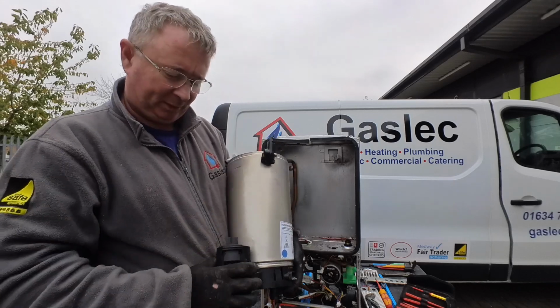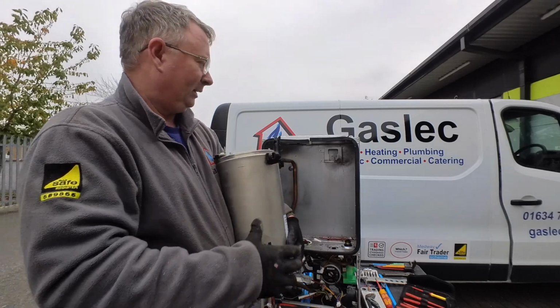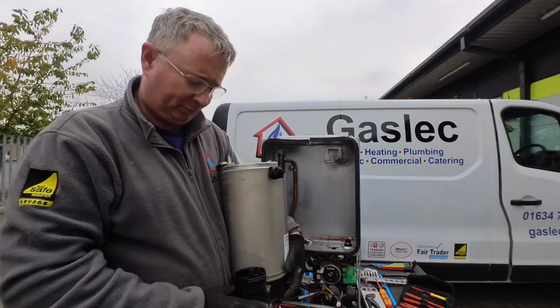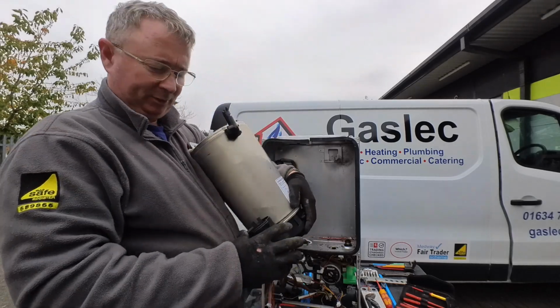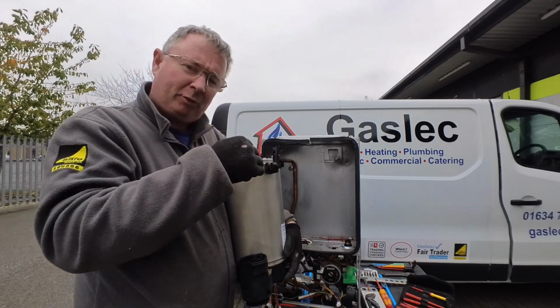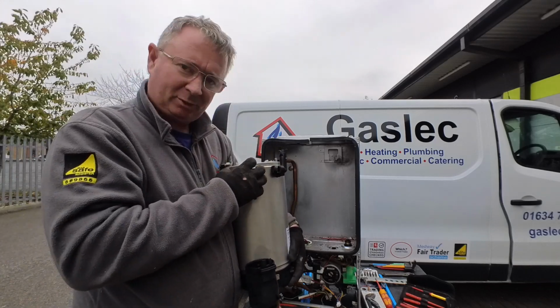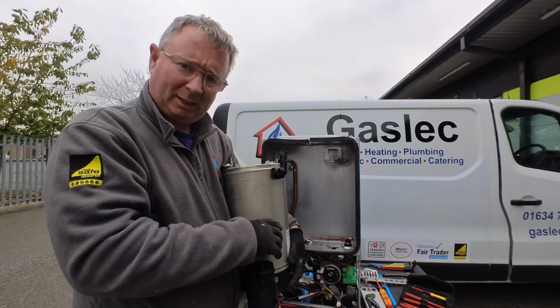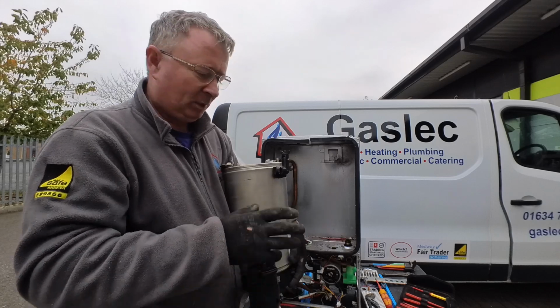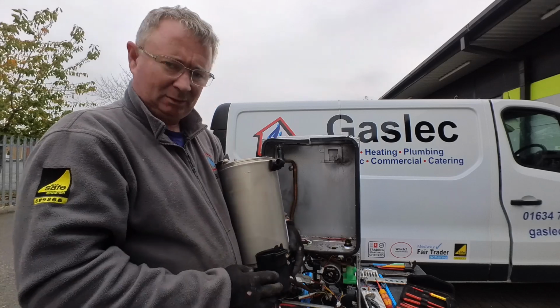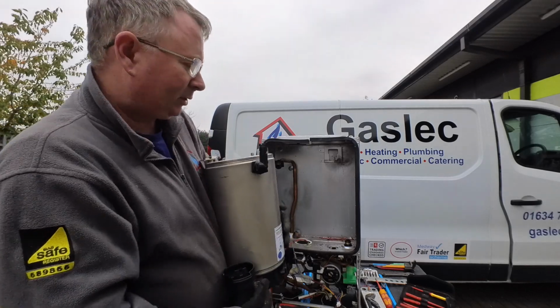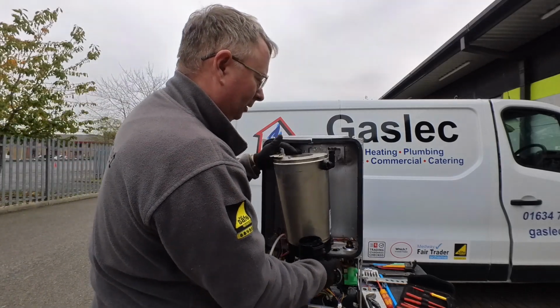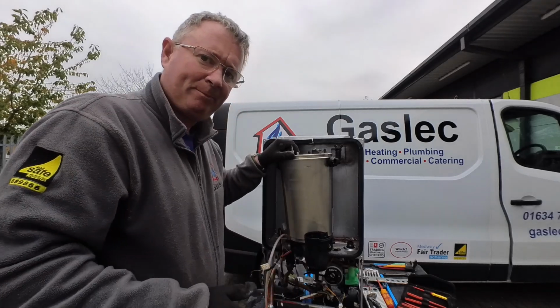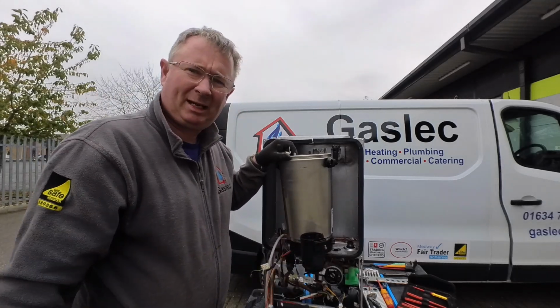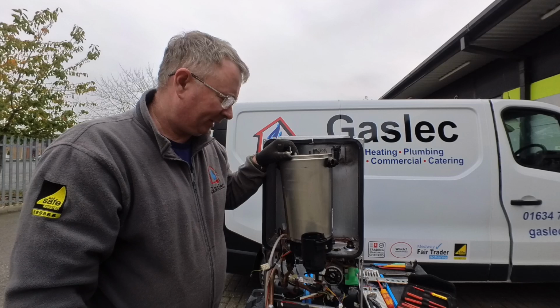This is the flue part that comes up to come out the top of the boiler, which I took off earlier. There's a flue stat just there, so if the flue's getting too hot - in other words too much heat coming through the heat exchanger into the flue - and all the flue parts are plastic, even this bottom piece, if that becomes an issue the flue stat will lock out, kill the boiler, and turn the gas valve off.